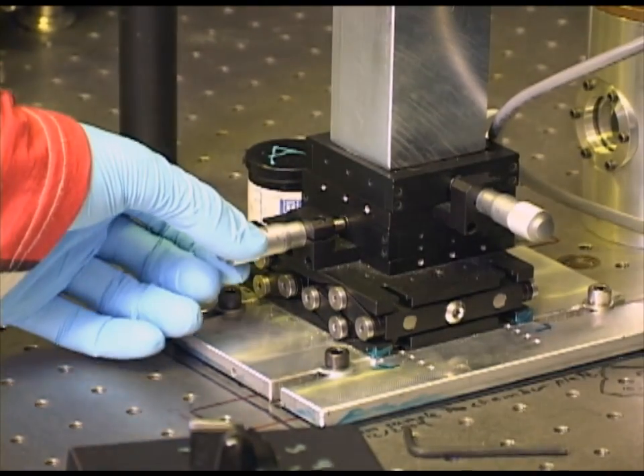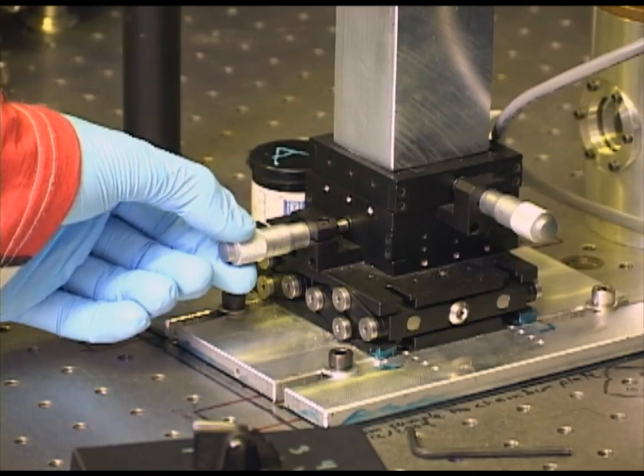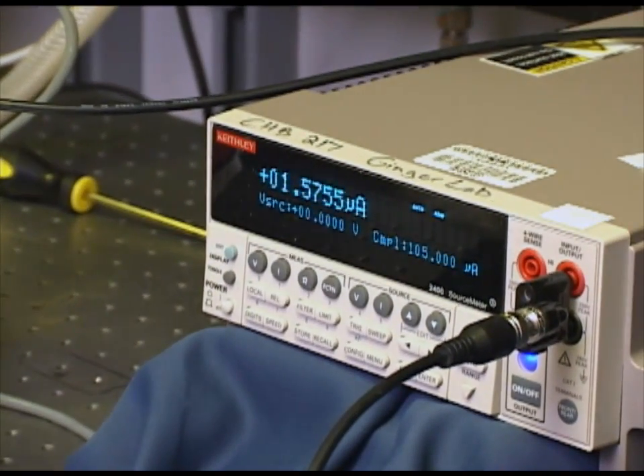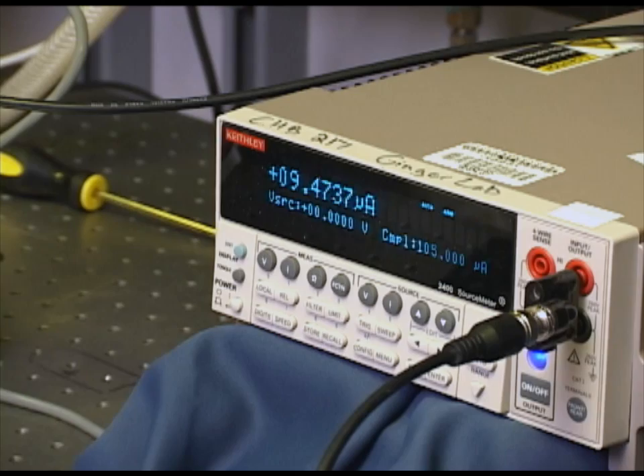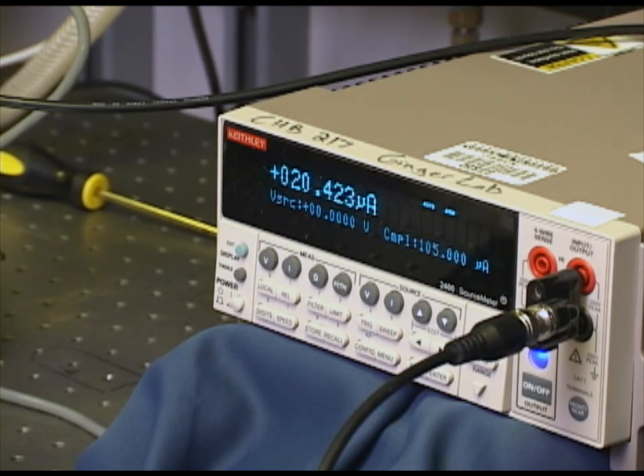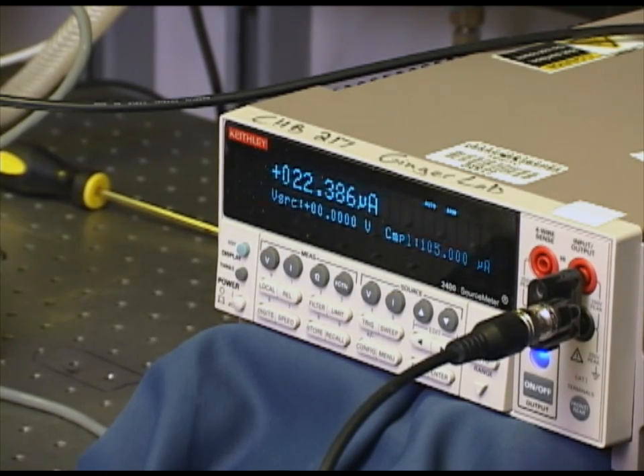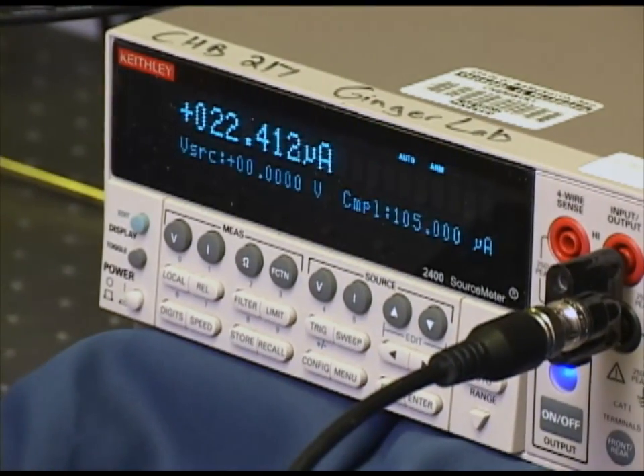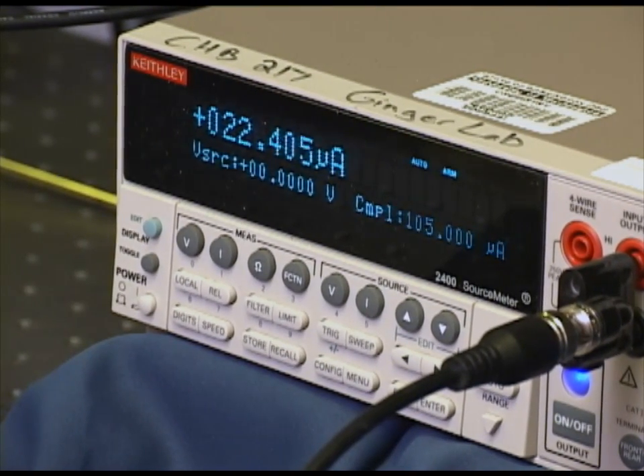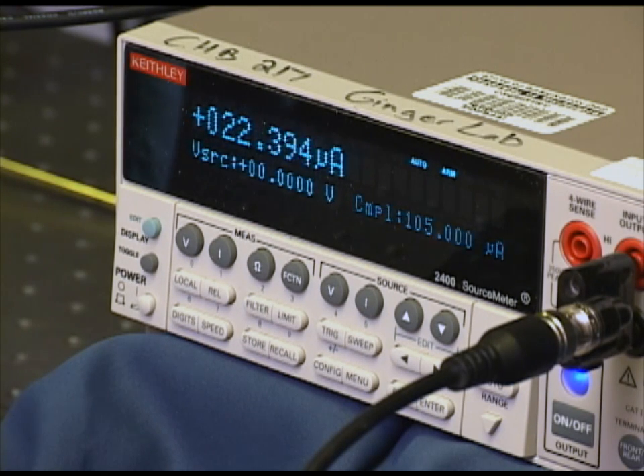We can see that if I move side to side, the current goes down pretty rapidly. This is an easy way for us to align things reproducibly by just finding the maximum photocurrent at a given wavelength. So right now, for the given monochromator settings of our lamp and the given power settings from our lamp supply, this particular photodiode being masked off to a certain area is giving us 22 microamps. And since we know the masked area of our mask, we can determine a photocurrent density as well.